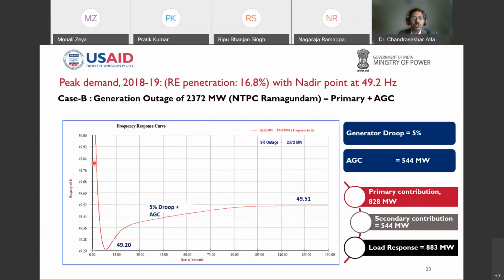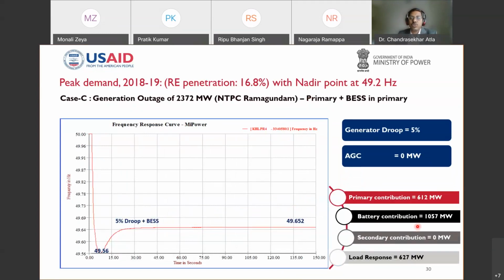So the next case is where we don't want to deploy much of the primary. So the same primary is there, and we added the secondary contribution. The frequency at which it arrests, what we call the nadir frequency, is still 49.2, but after 30 seconds, secondary reserves start deploying into the system. My frequency improved from 49.3 in the previous case to 49.5 in this case, with support from the secondary reserves. So that is the benefit to the system if we enable secondary reserves. Taking the third case, if you don't enable the secondary reserve, but allow the BESS to operate into the primary, here is a very interesting aspect we observed from the simulation results.